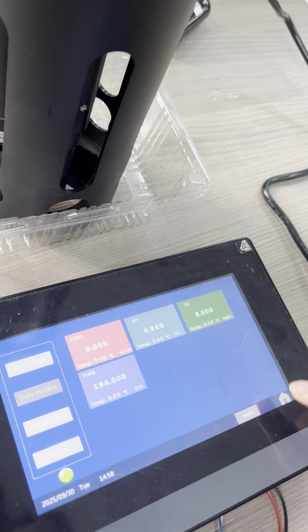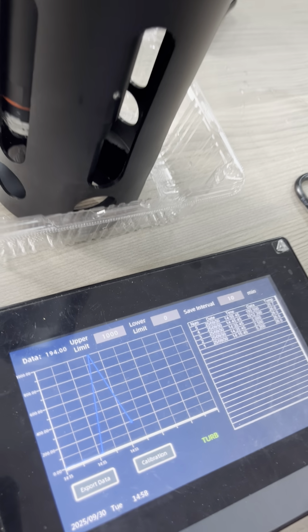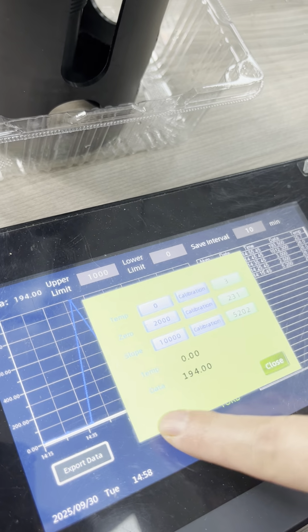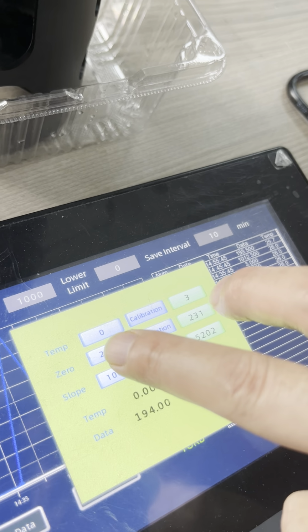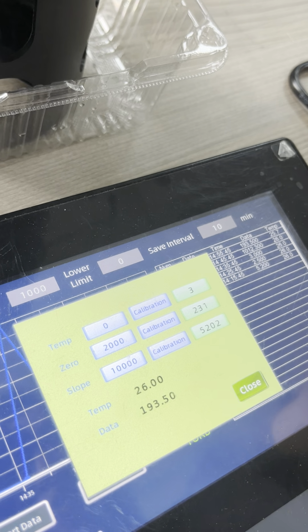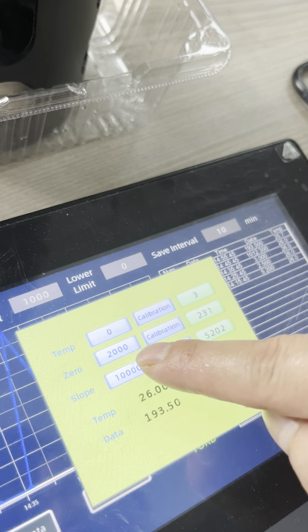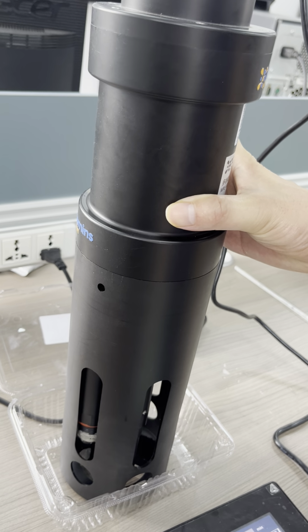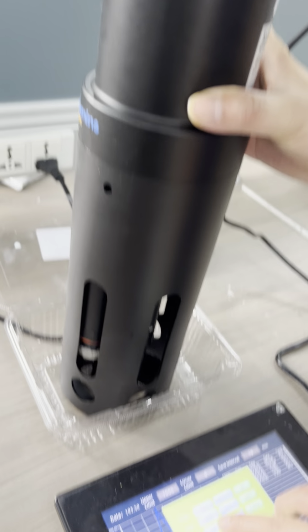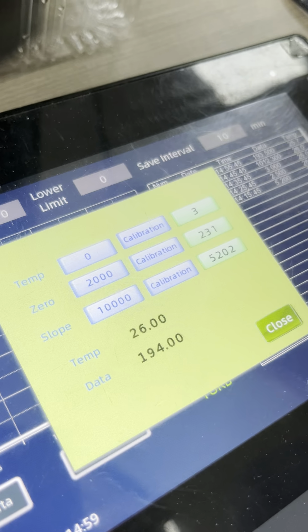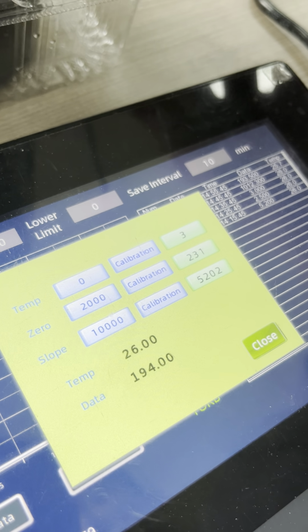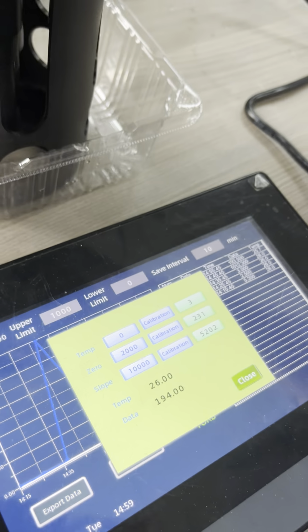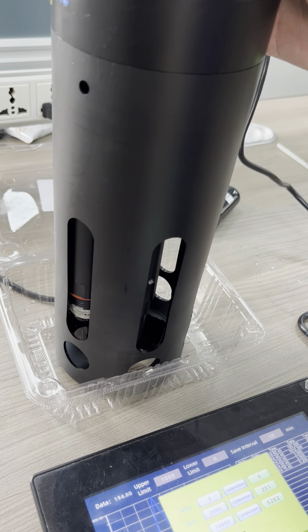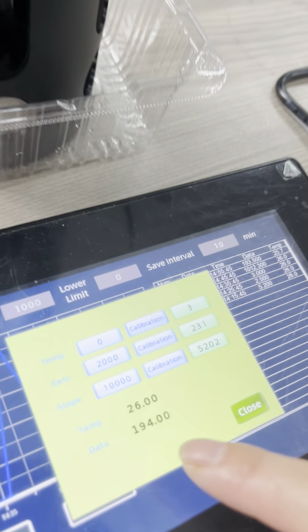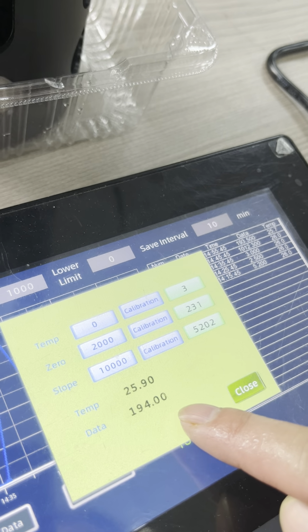We get back to turbidity calibration. Click calibration. The temperature calibration is not needed. We just do the zero calibration. Since the range you bought is 1000, we need to do zero calibration at 200 NTU standard solution. You put the sensor into 200 NTU standard solution. Then after 3 minutes, the data will be around 200.